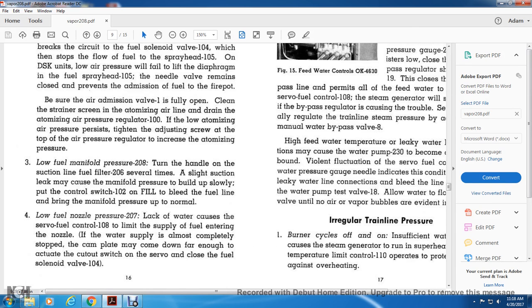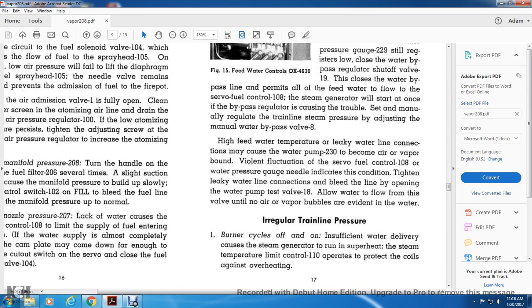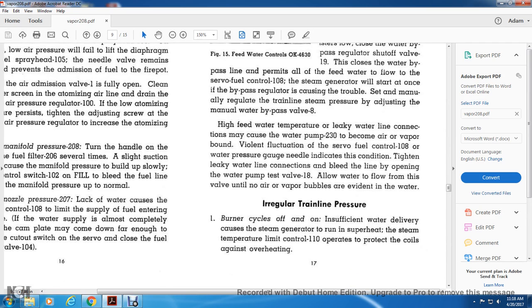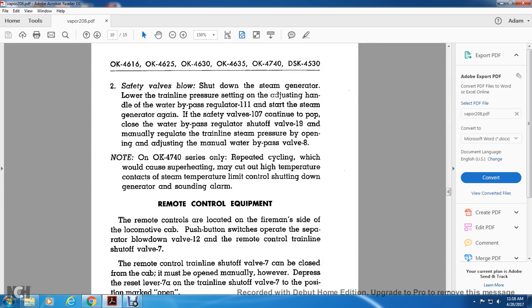Alright, irregular trainline pressure. One: burner cycles off and on: insufficient water delivery causes the steam generator to run in superheat. The steam temperature limit control 110 operates to protect the coils against overheating. Two: safety valve blows. Shut down the steam generator, lower the train line pressure setting by adjusting the handle on the water bypass regulator 111. Start the steam generator again.